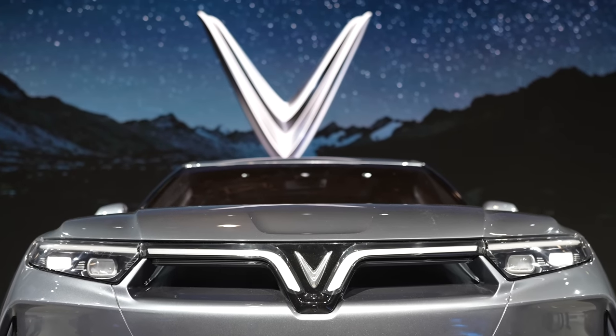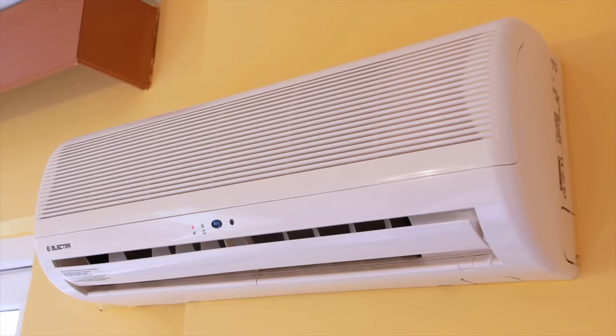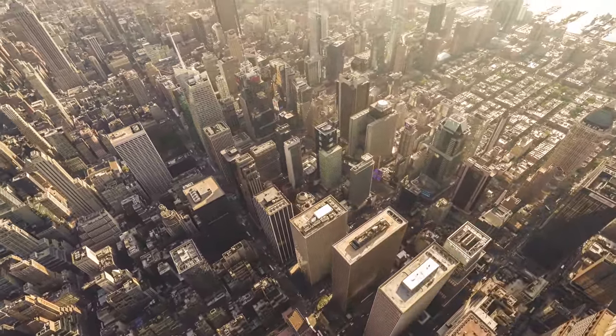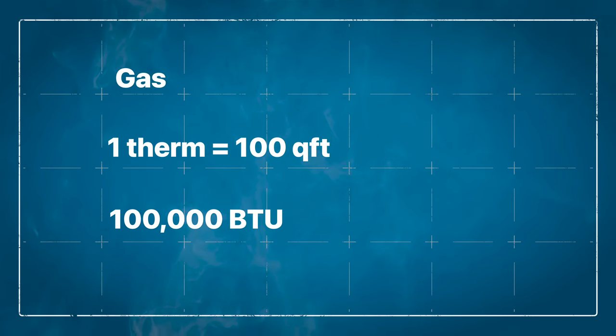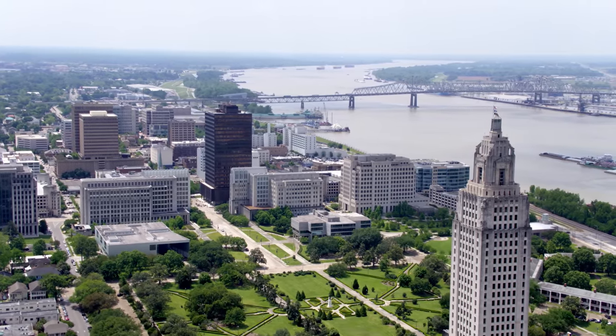For the average person living in the US, over half of your annual energy bills go toward heating and cooling. Most people favor natural gas because on paper it seems significantly cheaper than electricity. Gas is measured in therms — one therm equals 100 cubic feet of gas or 100,000 BTUs, which is the same as about 30 kilowatt hours of electricity. Hypothetically, if one therm costs 60 cents, electricity would have to cost roughly 2 cents per kilowatt hour to be comparable. But even in Louisiana, which has some of the lowest electricity rates in the country, they still pay roughly 7 cents per kilowatt hour. Generally with all factors considered, natural gas prices are two to three times lower than electricity.